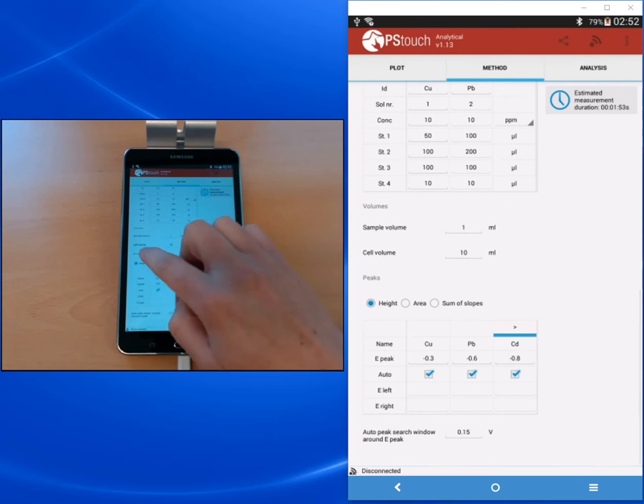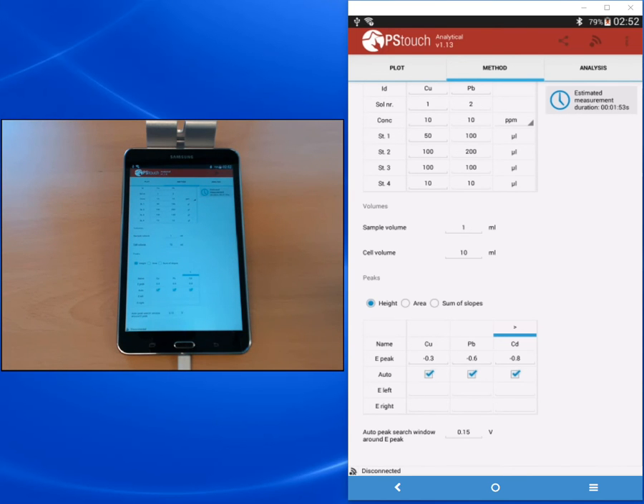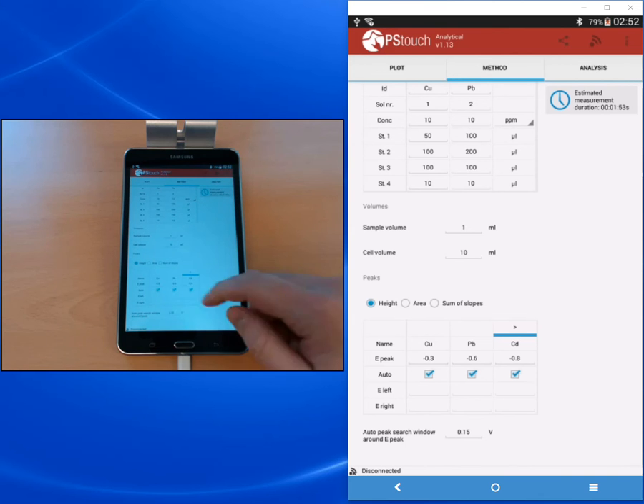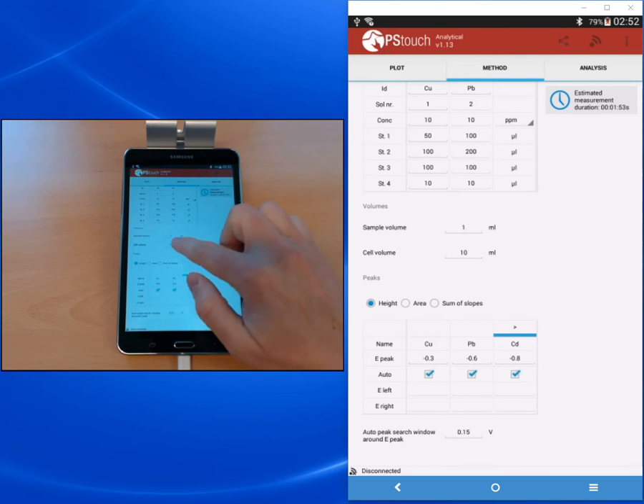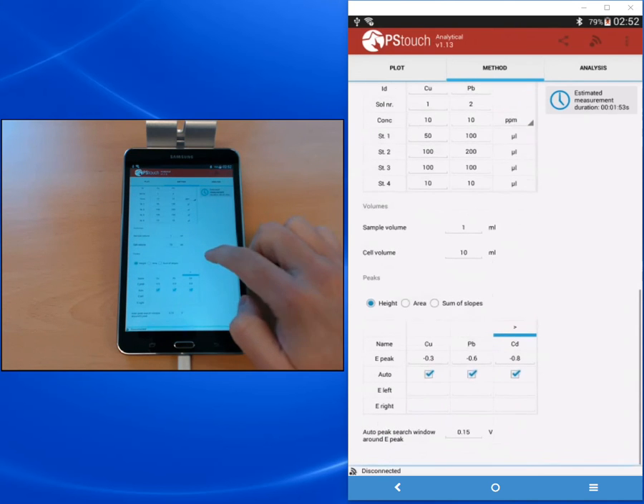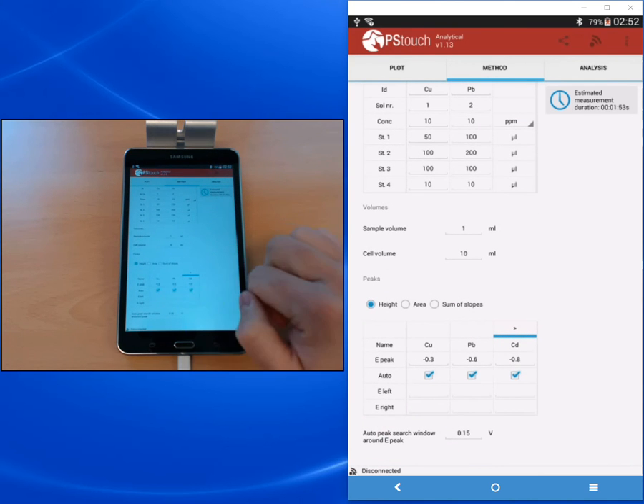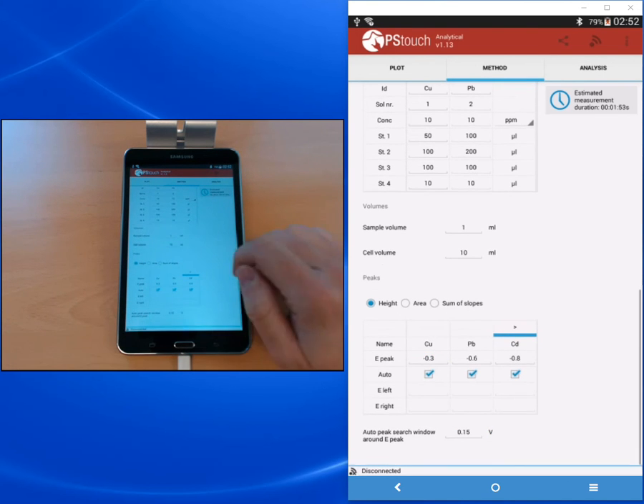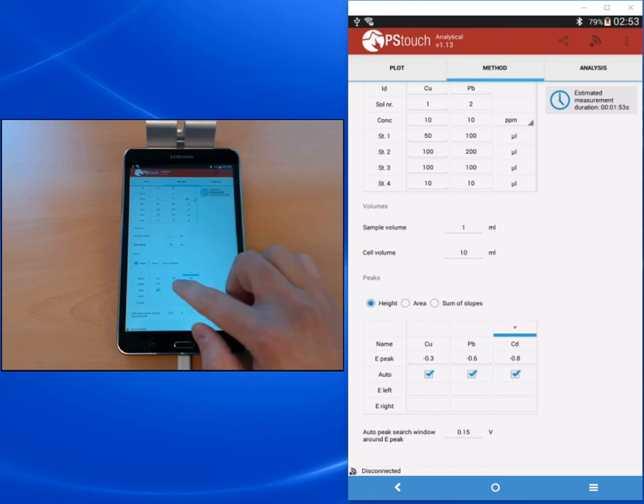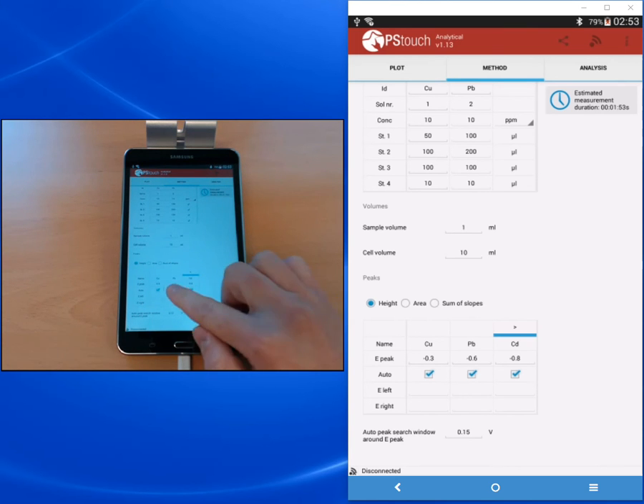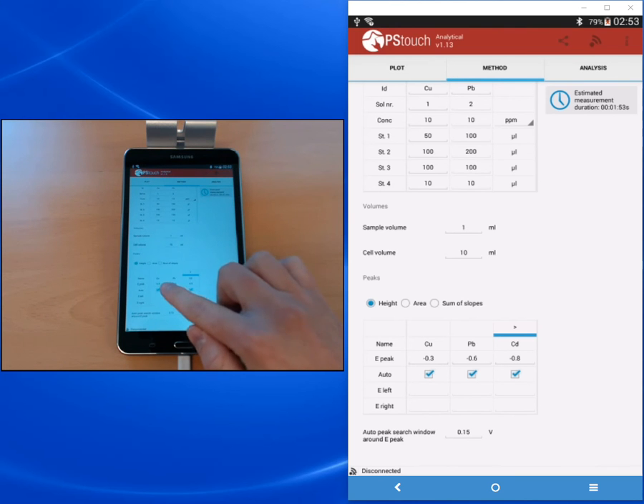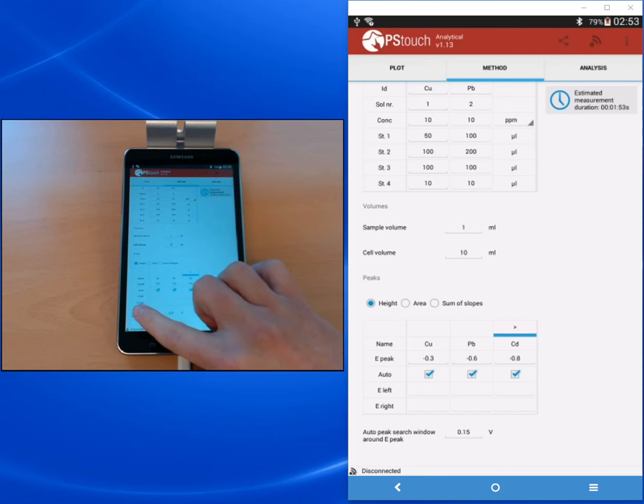Below that we find the peaks settings. This is how you correlate your signal with your concentration. You can choose different options. Usually you choose the height, and you see the names in the name row. Below that you find the e-peak where you enter the value where we expect the peak for that analyte. Then the software will search for the copper peak at around minus 0.3 volts plus minus the search window which is 0.15 volts. It will look around that value for the peak; it's an automatic peak search.